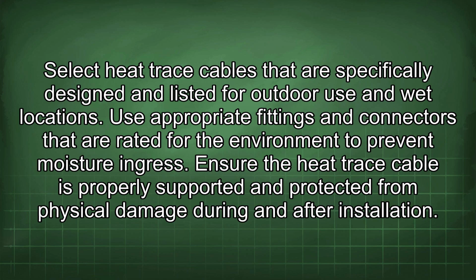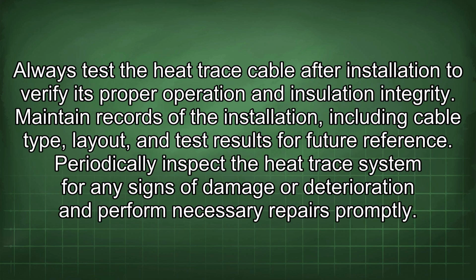Use appropriate fittings and connectors that are rated for the environment to prevent moisture ingress. Ensure the heat trace cable is properly supported and protected from physical damage during and after installation. Always test the heat trace cable after installation to verify its proper operation and insulation integrity. Maintain records of the installation, including cable type, layout, and test results for future reference.